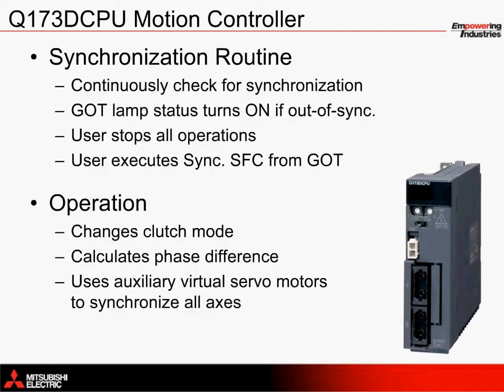The synchronization routine continuously checks the relationship between the master encoder and each of the slave servo axes in the background. If the encoder becomes misaligned with the position of a servo axis, or vice versa, a lamp on the GOT turns on to signal that the system is out of sync.